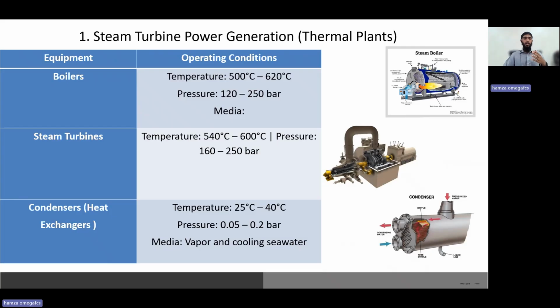So the conditions that we see in such a power generation system, namely in the boiler, are temperatures going up to 500 to 620 degrees Celsius. This is high pressure steam. Pressures that we see here are 120 to 250 bars, where the media is water. In steam turbines, we see temperatures of 540 to 600 degrees Celsius, the pressures being 160 to 250 bar. Mind that this steam is superheated steam that is being introduced to the turbines. And then we see a temperature of 25 to 40 degrees Celsius for the condensers, and pressures of 0.05 bar to 0.2 bar. Here the media is vapor and cooling seawater.